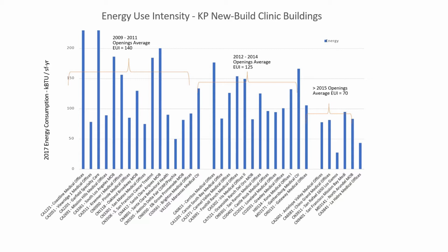So I want to show you a couple years' worth of buildings leading up to this. Most of our construction in the last 8 or 10 years has been these clinic buildings, and starting in 2011 we've had a pretty aggressive energy program for those. Our first step is doing energy models on every building, so we have energy targets, and for outpatient buildings the target is 50 EUI. We then measure the results of every building and compare them to those energy models.